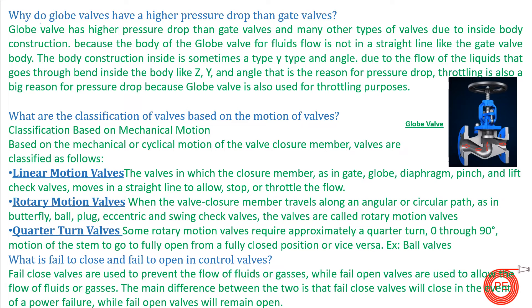The next question is: why do globe valves have a higher pressure drop than gate valves? Globe valves are basically used for controlling flow as well as for on/off service. Globe valves have a higher pressure drop because of their construction — the valve body is designed such that fluid has to flow in a zigzag motion, in a Y-direction or Z-type direction. Because the flow has to change its direction many times, there is a considerable pressure drop inside the valve.